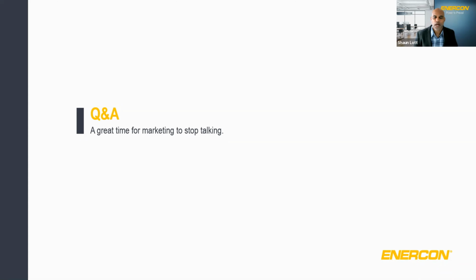And the next question is, can you apply UL marking labels in the field after control panels are shipped from the manufacturing facility? Oh, great question. That would be kind of yes and no. No, right off the bat, because once the product leaves the facility, you can't just go out in the field and say, oh, hey, we forgot to put this label, let me go stick it on. There is a process, however, to do that. You have to request a UL field audit, which means the manufacturer's representative needs to go out to that field location. They have to schedule an auditor to do a field inspection.